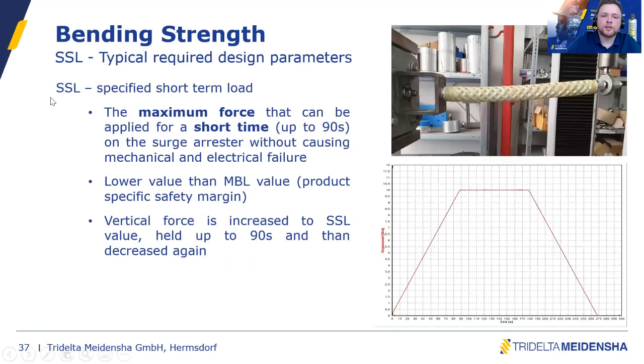Then for porcelain housed surge arrestors, but even more for polymer housed surge arrestors, the SSL value plays a big role. SSL is the specific short-term load, which means the maximum force that can be applied for a short time on the surge arrestor without causing a mechanical or electrical failure. And typically the test looks like this. Here we have an SBKW design, and we pull on the top. We pull until the SSL value is reached. And then we hold this value, and then we decrease the value to 0 again, and afterwards the surge arrestor has to be electrically and mechanically intact.